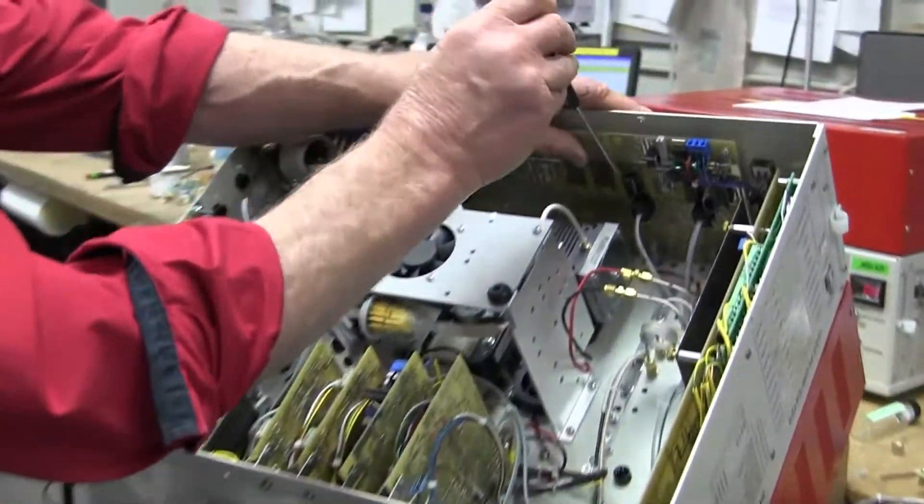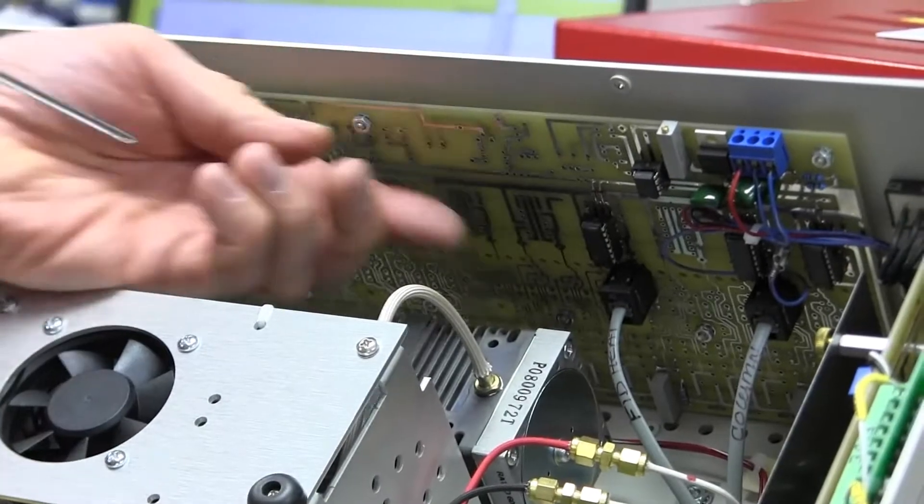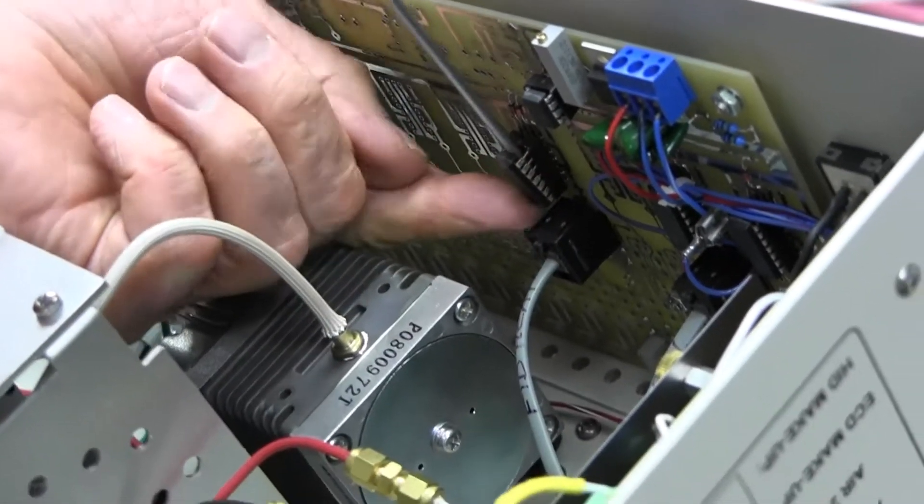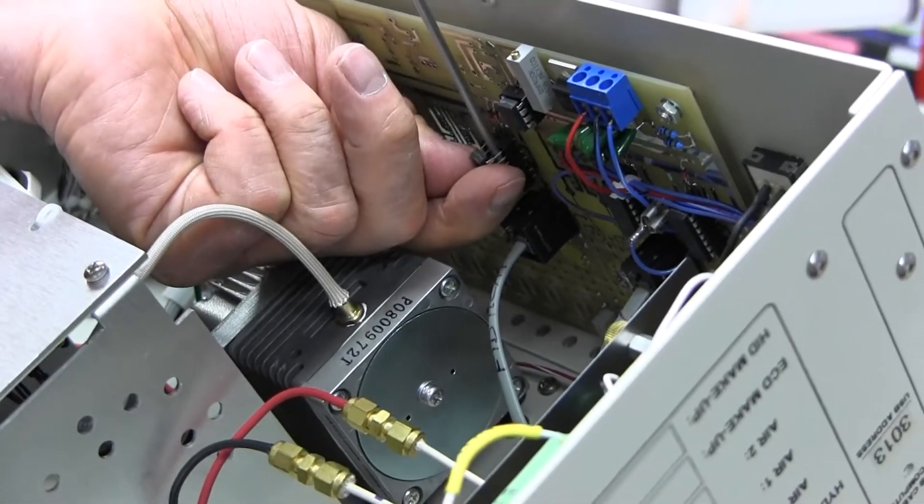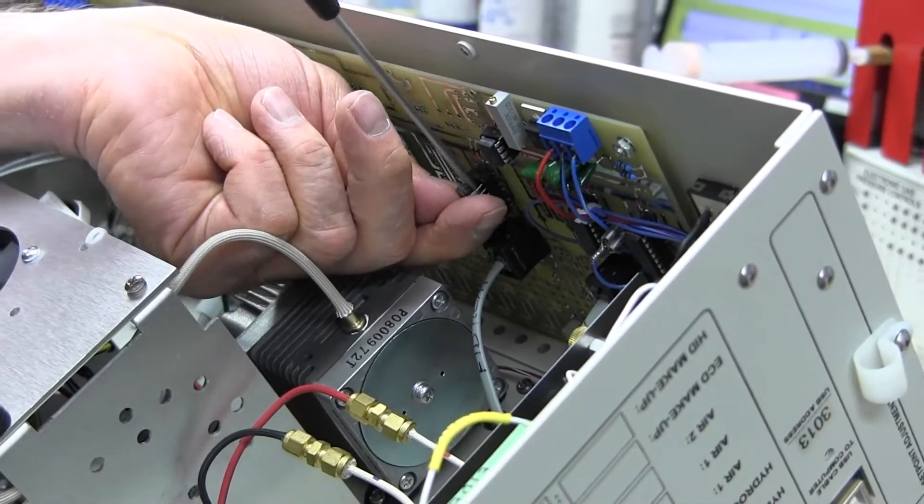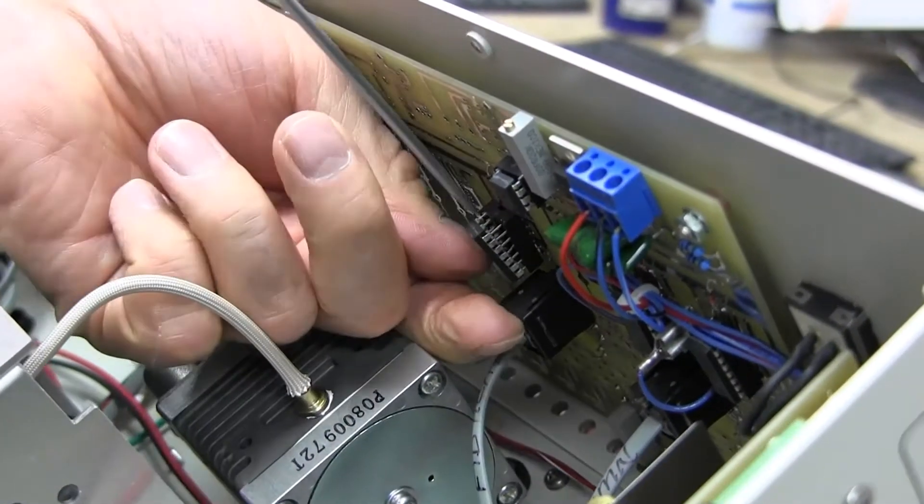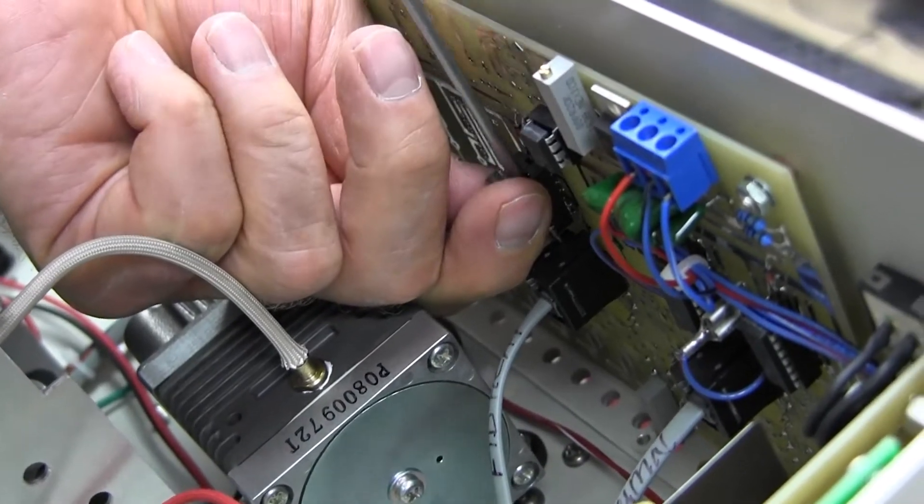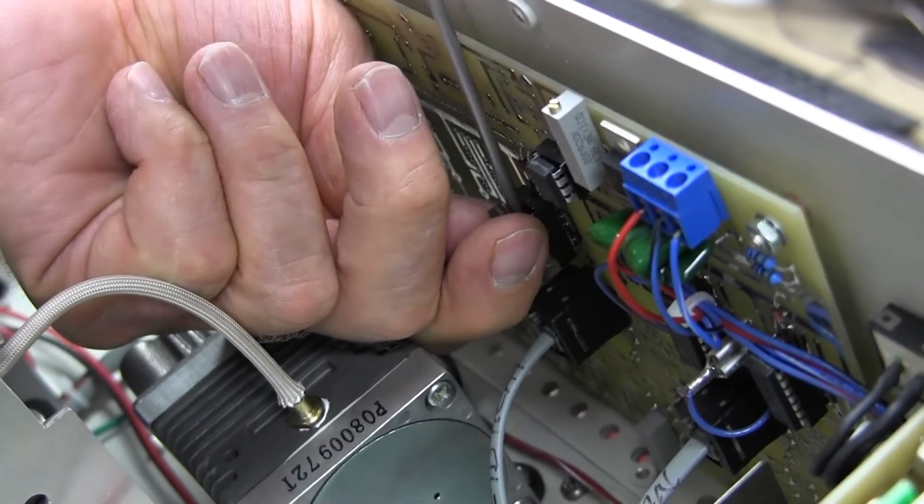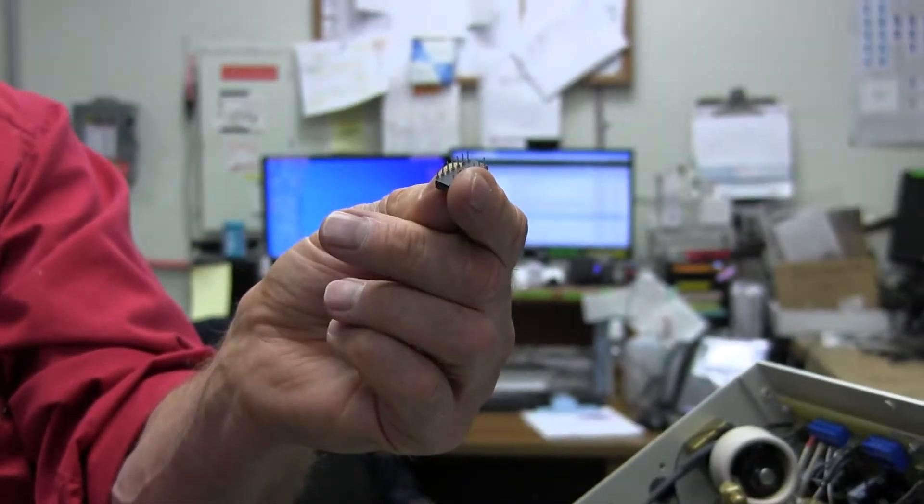It's easy to do when it's right here. It's a little harder to do when it's mounted in the GC, but this is what you would do, the same thing. You take the screwdriver, and you kind of wiggle it a little bit to try to separate the chip from the socket, and then you kind of try to wiggle it out gently, and not bend the legs. So if you bend the legs, you can sometimes straighten them out, but it's best to try not to bend the legs. So there it is. I think I've got the chip out. I didn't bend the legs hardly at all, but I've been doing this a long time. Anyway, if you bend the leg, just try to bend it back with a little pair of pliers or tweezers or something.